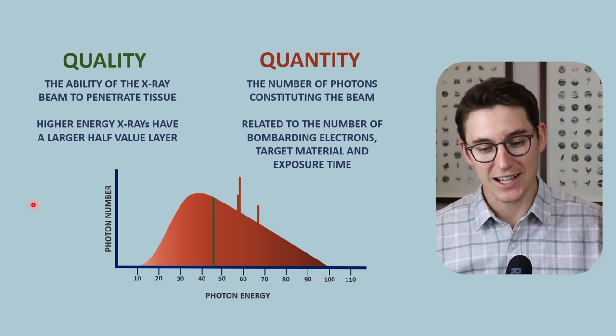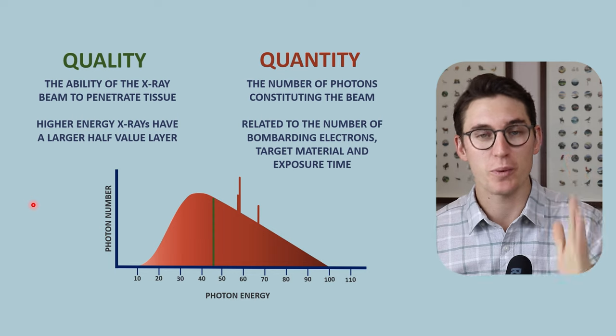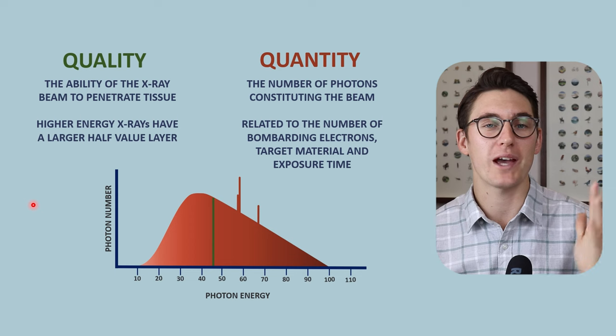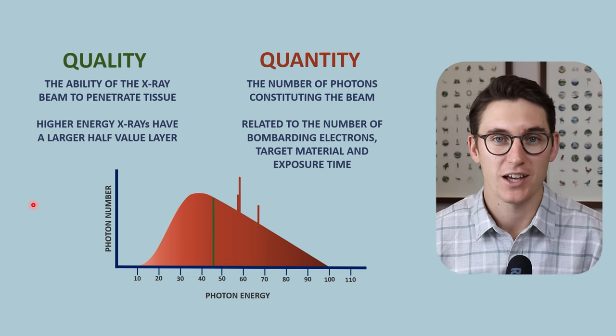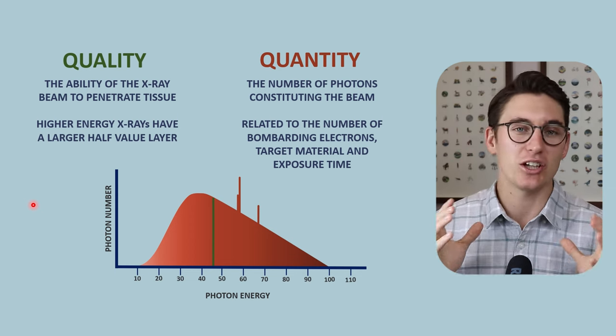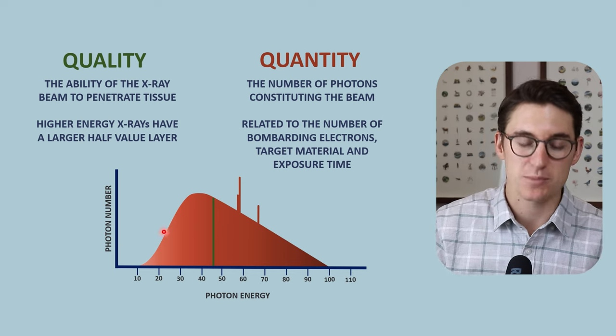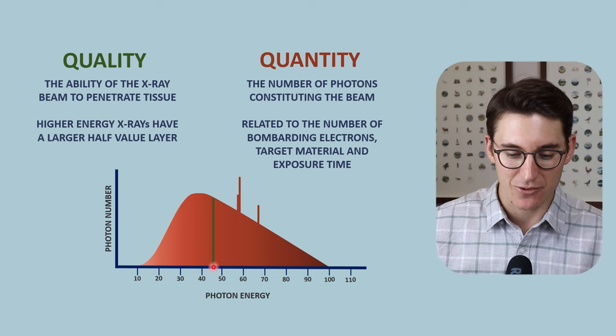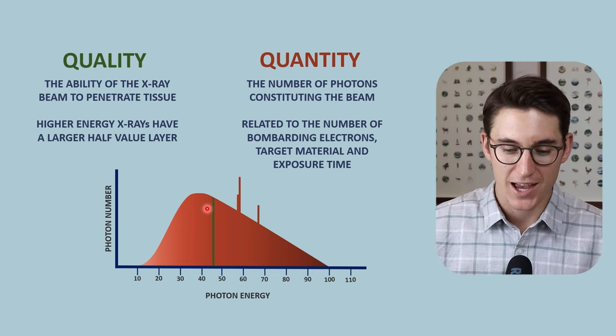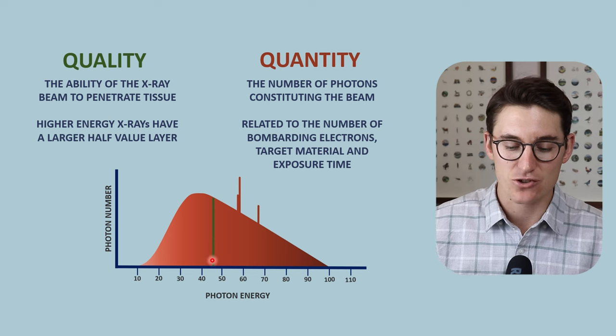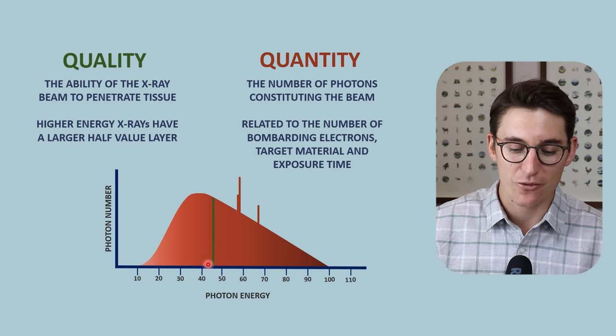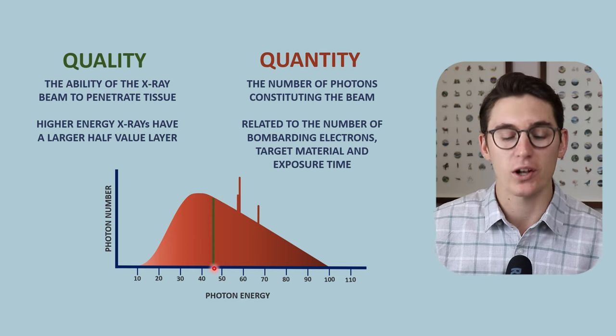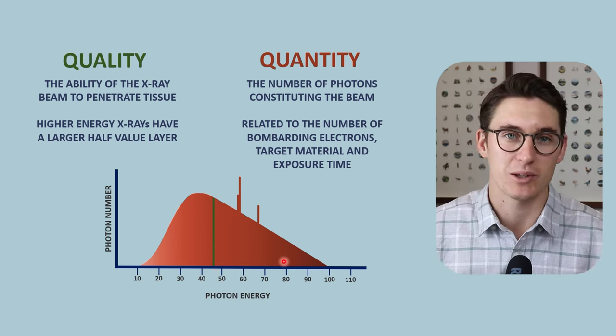X-ray beam quality is the ability of an X-ray beam to penetrate a tissue, and we use what is known as a half value layer as a proxy for X-ray beam penetration. That refers to the energy of that X-ray beam. When we look at an X-ray spectrum like this, we will average out those energies and assign a value to this specific X-ray spectrum. We call that value the X-ray beam quality - the average energy of that spectrum here. This green line here represents the quality of this specific X-ray beam spectrum.